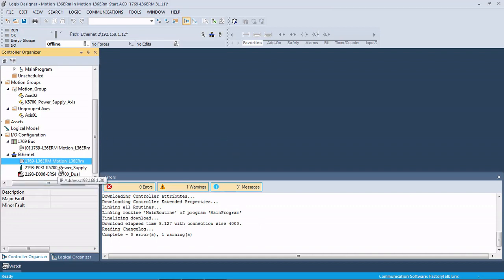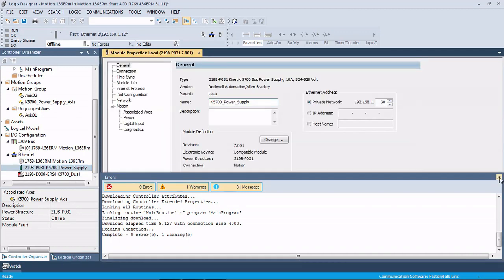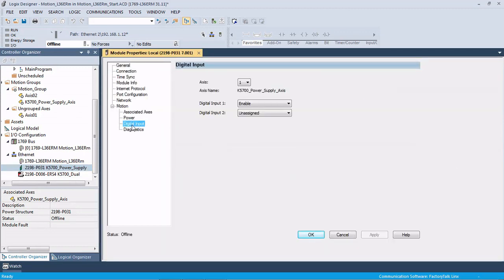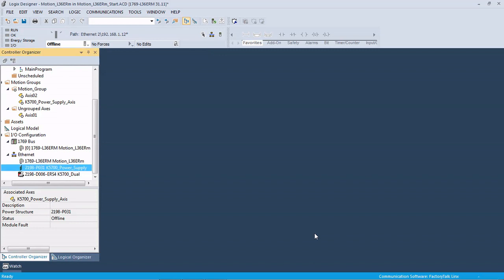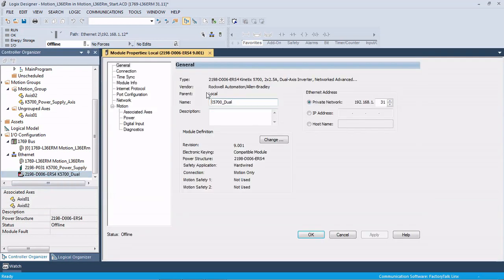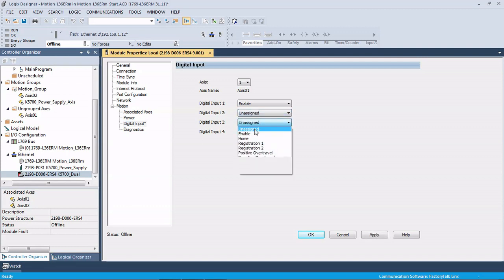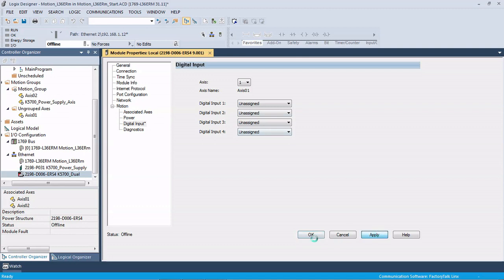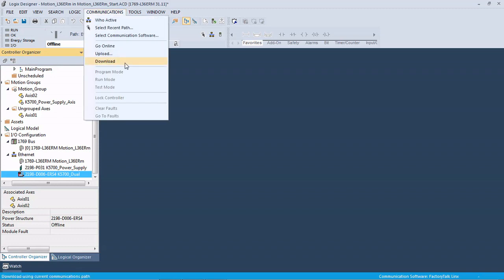The next thing, and this is for the demo more than anything, is in the drives, the digital inputs. By default on the power supply, digital input one is set to enable. That's not wired in our demo box we have here, so I'm going to make that unassigned. And then also in the drive, under the digital inputs, same thing. These aren't wired in our demo, so I'm going to make them all unassigned. Now we are ready to download.